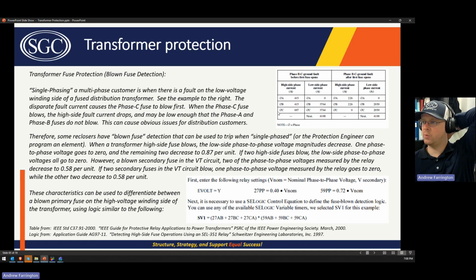This is what I was talking about, where the phase that is connected to both of the faulted phases on the low side gets more current than the other two. Okay, so this fuse would see 697 amps for this particular fault, which means that fuse is going to blow first because it sees more current. And then after that fuse blows, it knocks down the current on the low side, but also knocks down the current on the high side. So it's possible that this fault current isn't enough to blow the remaining fuses now that this one is blown.